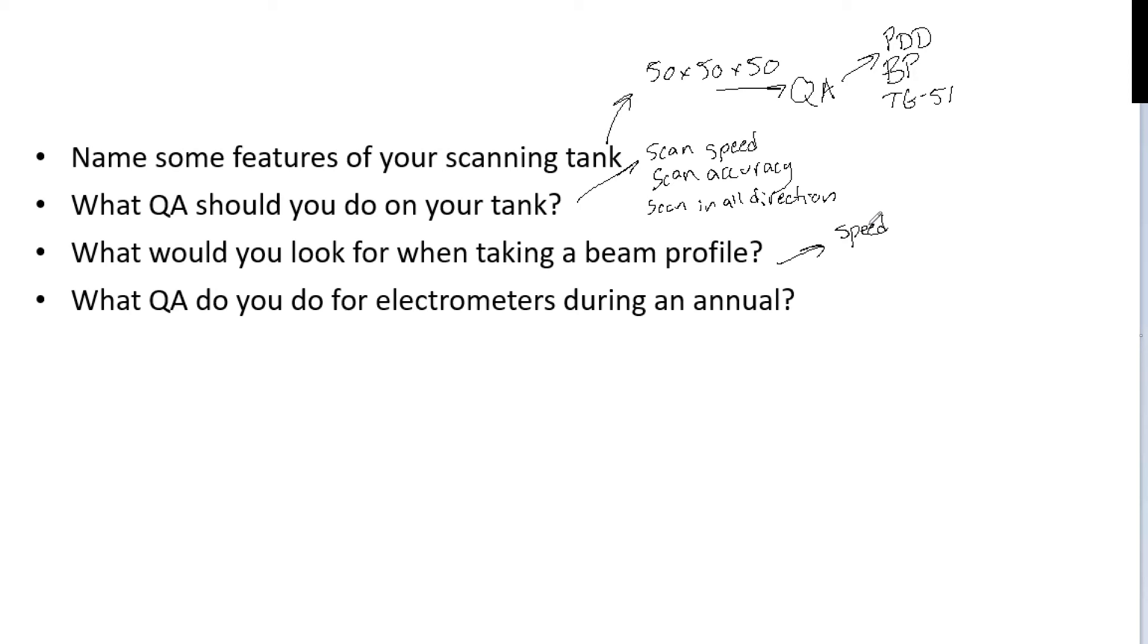You also want to be sure that the ion chamber is exactly in line. So I'm just going to put ion chamber position for this. If the ion chamber is kind of wobbly or it's not perfect, like the surface isn't set or when it's in the chamber, ideally it is straight, but so this is the correct and say incorrect here is say it's pointed down or something. That's obviously very, hopefully it's not that bad, but kind of exaggerated to prove the point. If there's a wobble or if it's at a degree, that's going to completely change your beam profiles and all of your readings.